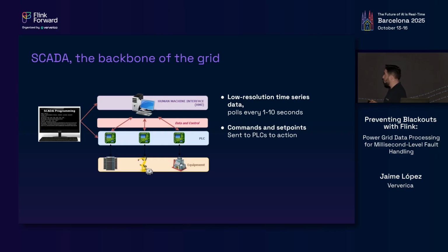But they work on pretty low resolution time series data. They're built for the era where situations happen and develop in minutes or hours. So a SCADA polling cycle is somewhere between 1, 10, or 20 seconds, which means that you have one data point every 1, 10, or 20 seconds. Very good in the 80s, in the 90s, not enough for now. Why? We're going to see a couple of good graphical examples of why.